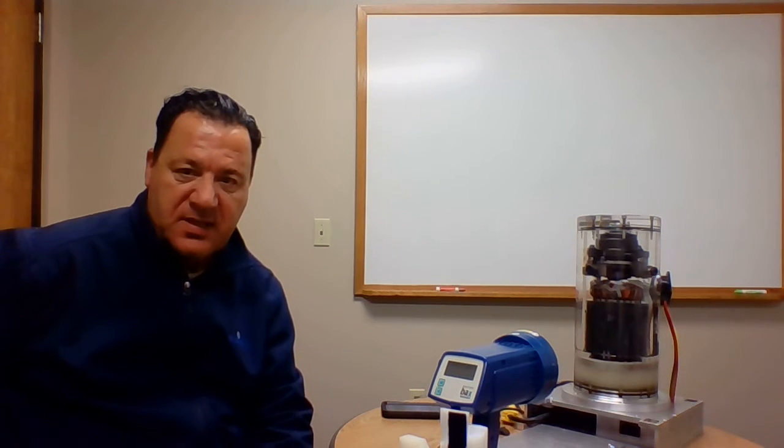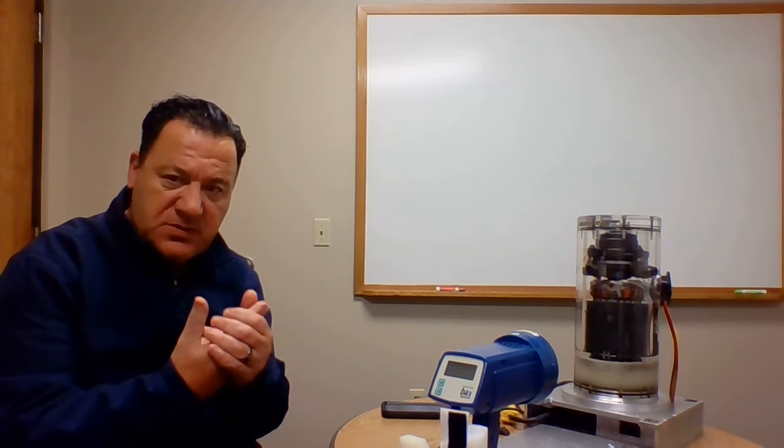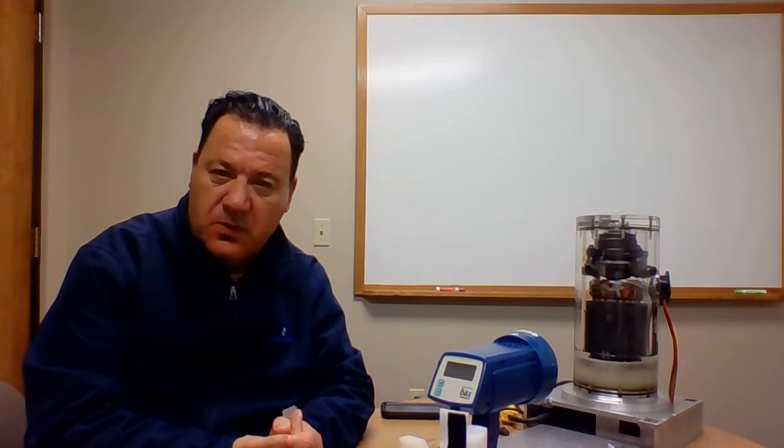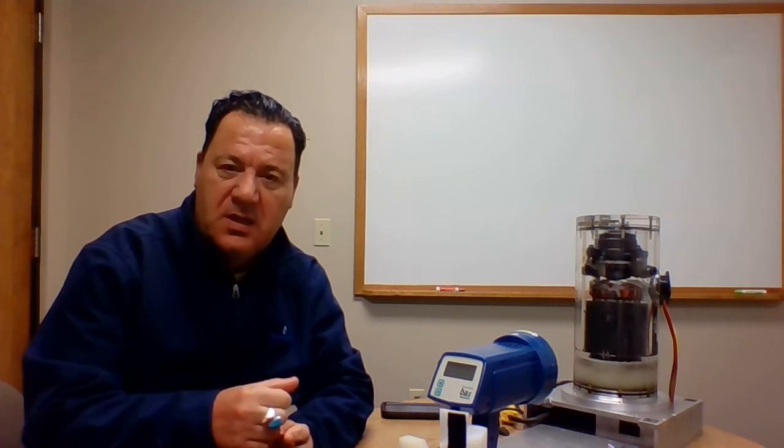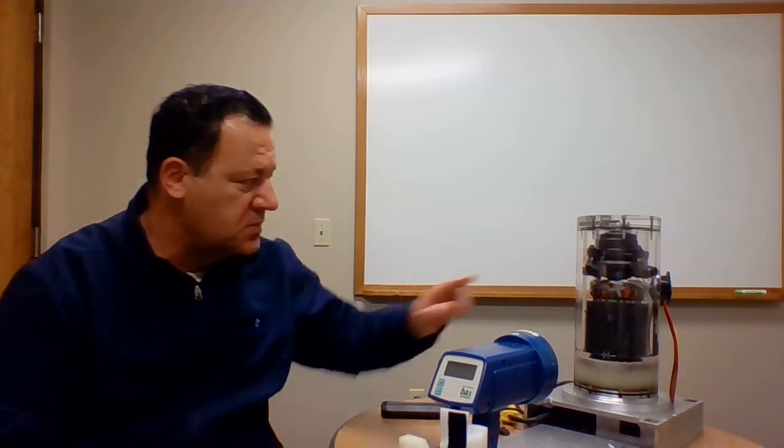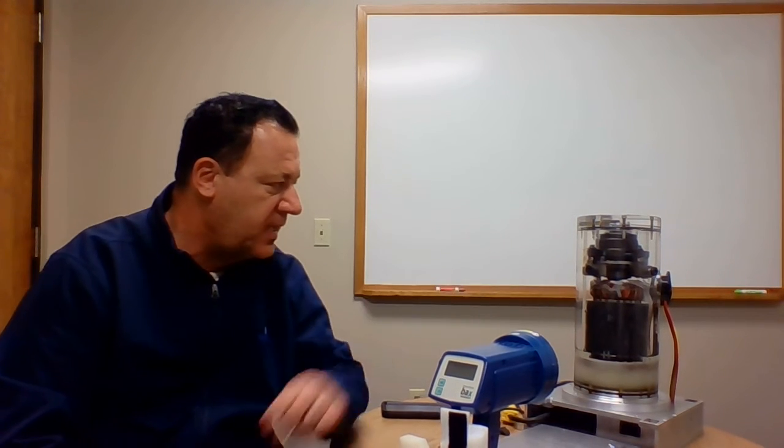As you know, we've talked about this before. We have the two scroll sets. The upper scroll, we refer to as the fixed scroll. The lower scroll is the orbiting scroll. On top of that is our floating seal. On the bottom of that is our Oldham coupling. We're sitting on top of this straddle bearing here.